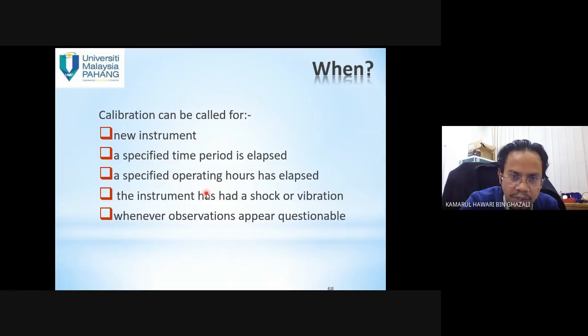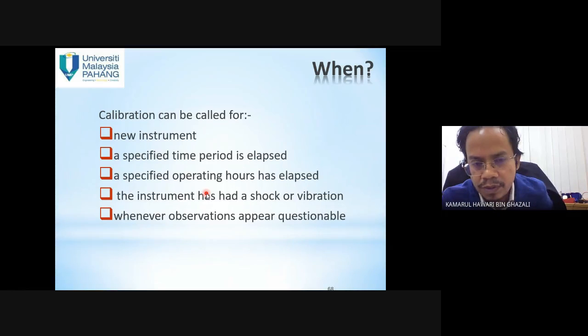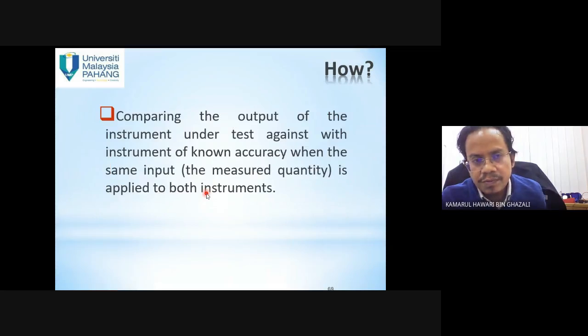So calibration can be called for when you have a new instrument, because the new instrument maybe has never been used for quite a long time. Also when a specified time period has elapsed, when a specified number of operating hours has elapsed, or when the instrument has had a shock or vibration. Whenever the measurements appear questionable, then we need to do a calibration.